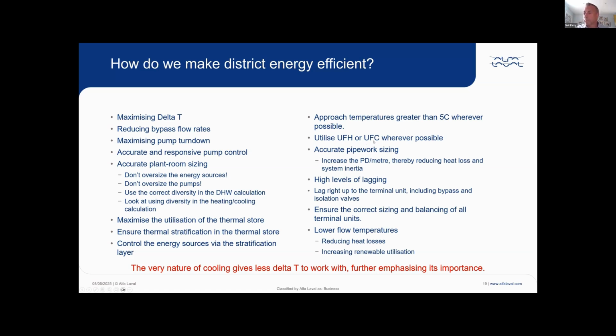Underfloor cooling gives you a much better performance, as does underfloor heating if it's a heating circuit. So look at underfloor wherever possible as the heat emitter, and then accurate pipework sizing, increasing the pressure drop per meter. It increases velocity, but it reduces the diameter of the pipes. And because these systems should be truly variable, we don't need to worry about erosion from high flow rates, because the high flow rate only occurs for a small period of time on that network. And then obviously, as you would expect, high levels of lagging, make sure we're not losing our cooling into the building where we don't want it, or into plant rooms, and so on and so forth. And then correct sizing of terminal units, and so on.